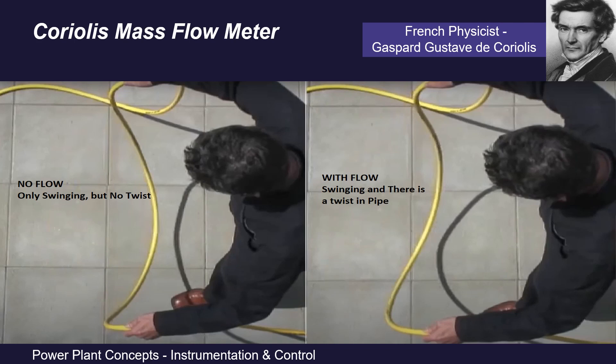Coming to Coriolis mass flow meters — the Coriolis mass flow meter works on the Coriolis effect, hence it is named so. As shown in the left side picture, a hose swings back and forth but does not twist. However, when water flow is turned on and water is forced through this swinging hose, the hose twists — as we can observe in the right side picture. The hose twists as a result of the changing angular velocity in the curved hose. That's the Coriolis effect in action.